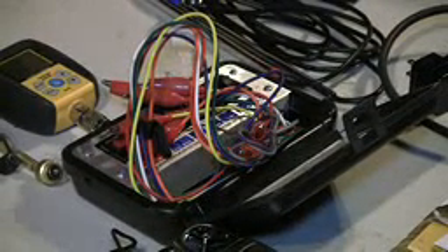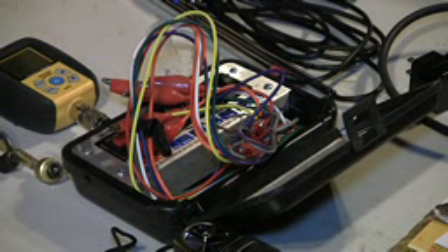Below that is something I recommend everyone get, even though it's not necessary but very nice to have - a ZipStat. Basically, the ZipStat is a remote control module that lets you operate the system without a thermostat, or without waiting a long time for the system to start up or shut down. You hook the wires up and can fire up your AC, fire up your heat, turn on the fan, check for continuity, check for shorts. It also has a built-in fuse circuit breaker - using the red and white wire connected to the fuse port where a 3 amp or 5 amp fuse goes, it acts as a fuse protector, which is great, especially when troubleshooting a short. I've used that a couple times and blown at least 20 fuses at one time, but because I had that in place, I didn't have to worry about it.